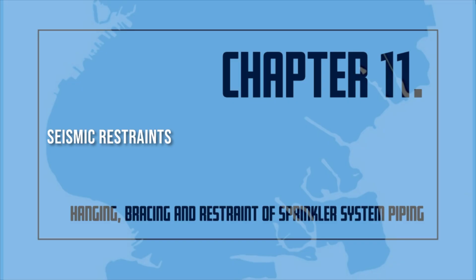To avoid damage to piping passing through holes in platforms, walls, floors, and foundations, a clearance of at least 2 inches shall be provided around the piping and the penetration. If this is not provided, a flexible coupling shall be provided within 1 foot on both sides of the wall, floor, beam openings, or platforms.